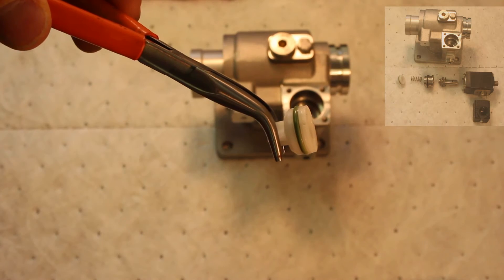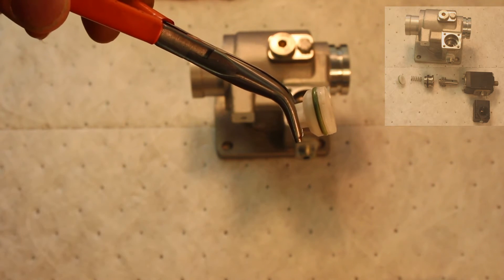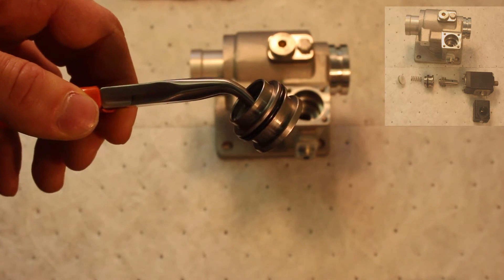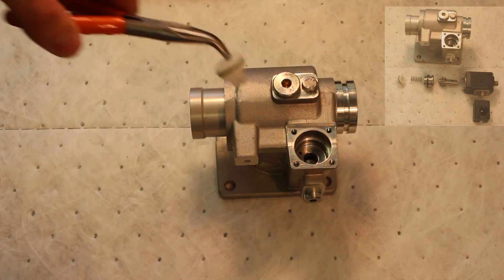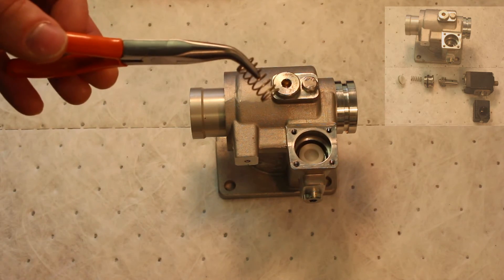Before installing the new spring and poppet, lubricate the o-ring on the poppet with grease such as white lithium or valvoline crimson. Do not use excessive amounts of grease as this may impede the operation of the solenoid poppet valve. Remove any excess grease from the top and the bottom of the solenoid poppet.